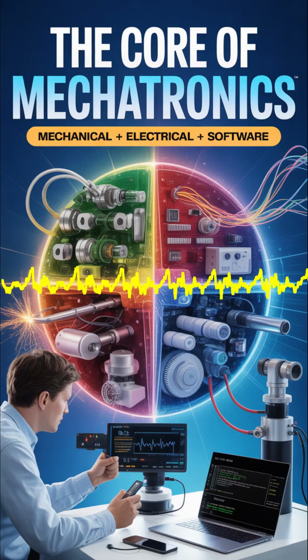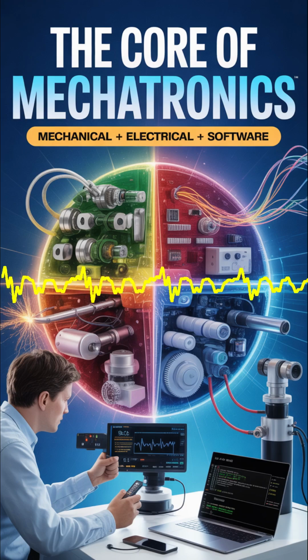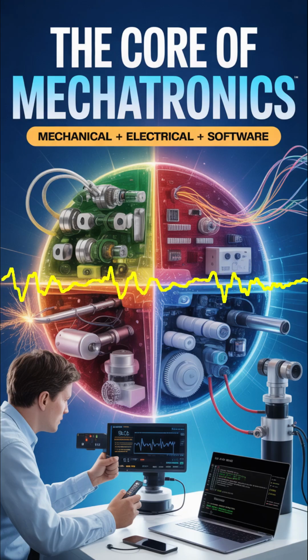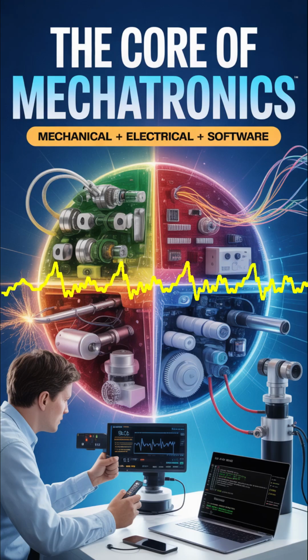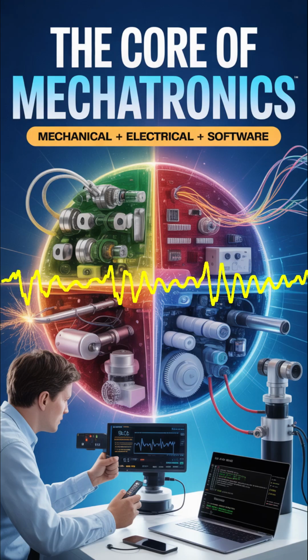Finally, environmental durability—something that seems obvious but trips people up. You have to define it in three ways: electrical durability, handling voltage spikes; physical durability, withstanding vibration, dirt, or pressure; and chemical durability, working in extreme heat or with corrosive salt spray or hazardous materials. Miss just one of those, and your multi-million-dollar machine grinds to a halt because of a $100 sensor.